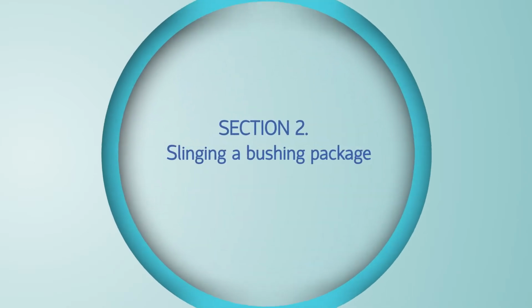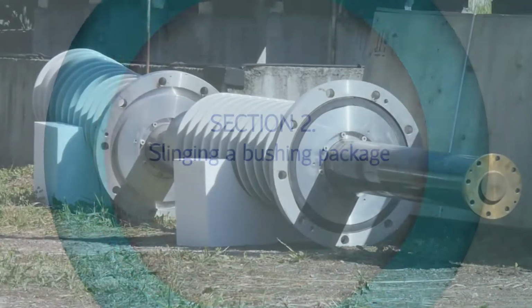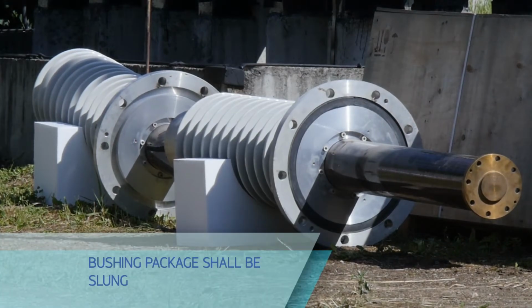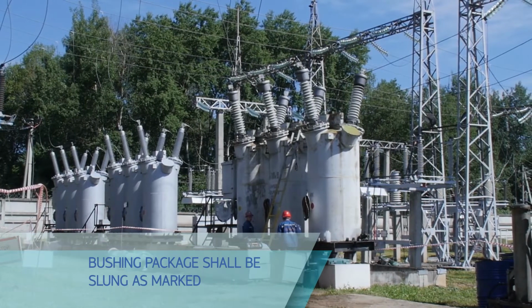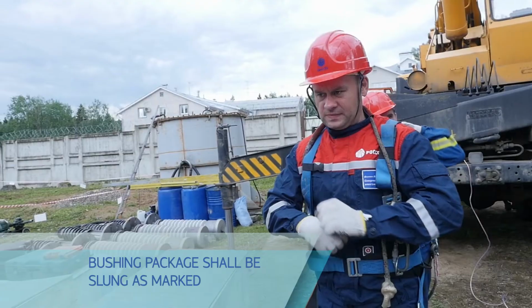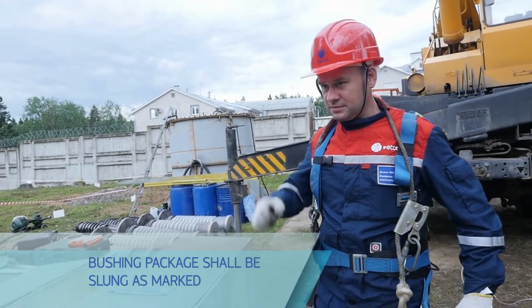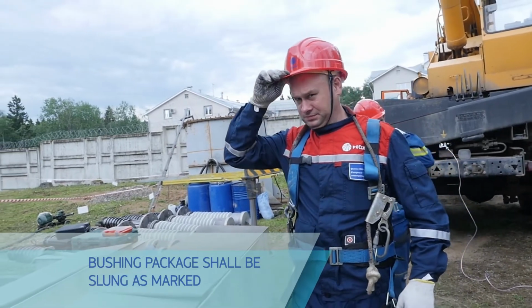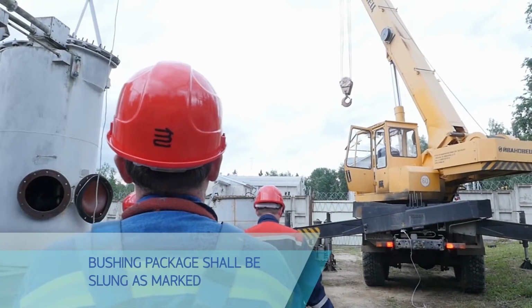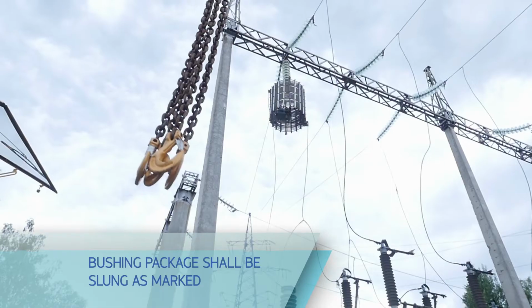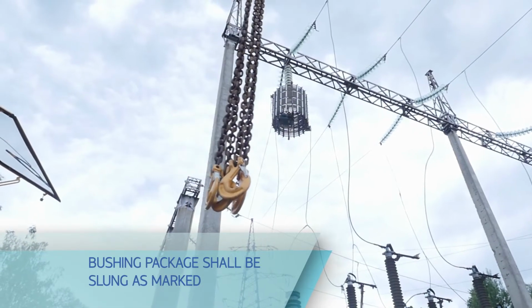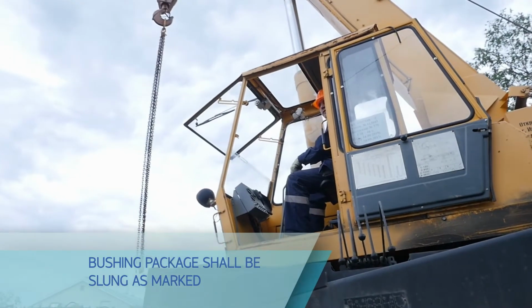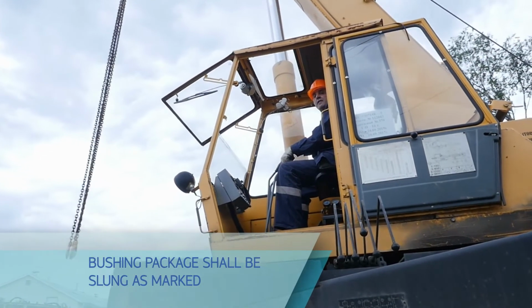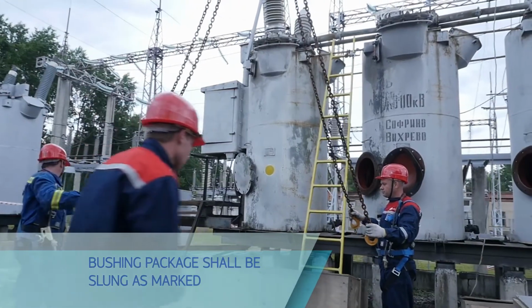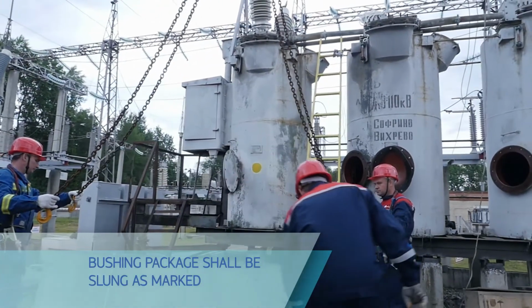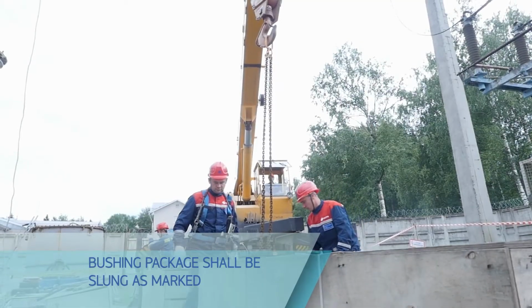Slinging a bushing package. Let us proceed to the high voltage bushing installation, namely to handling operations. Before unpacking the bushing, make sure that handling equipment can carry the item weight and is in order. Slings meet necessary specifications, are certified and intact. Slinging of bushing packages and bushings themselves, as well as their handling, shall be carried out by personnel qualified in terms of occupational health and safety. A bushing package shall be slung as marked on the side of the box.